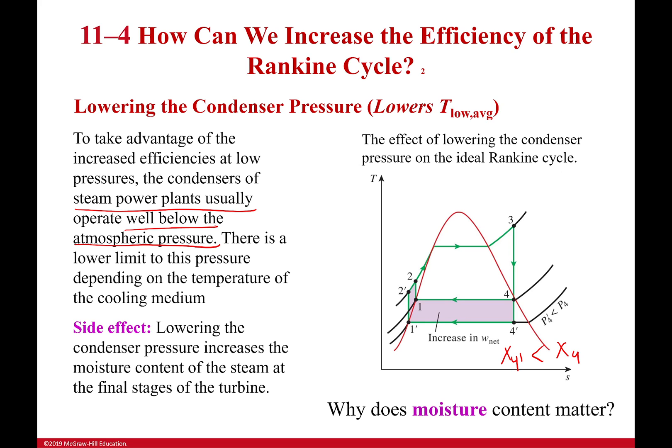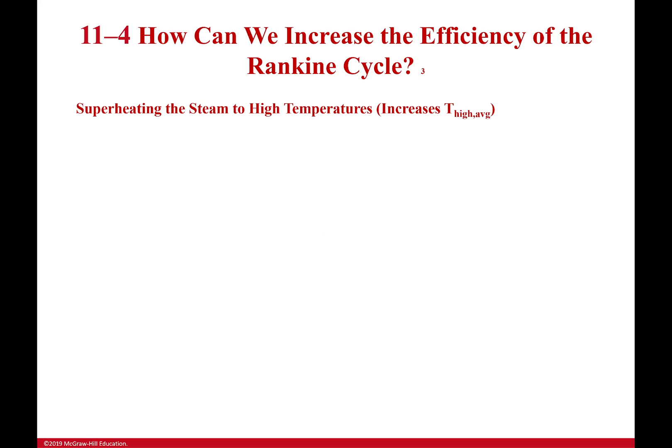Why does moisture content matter? Because remember, if you've got a fan and it's spinning really fast and it smacks into a water molecule, that water molecule can dent it, break it, cause it to crack and eventually cause it to completely break down. I always like to tell people that if you're talking about turbines, they're spinning ridiculously fast. And it's kind of like throwing sand into it because the water droplets aren't going to be that hard compared to how fast the fan blades are moving.